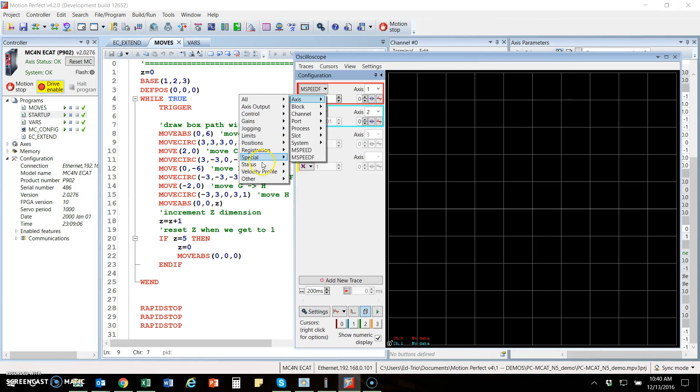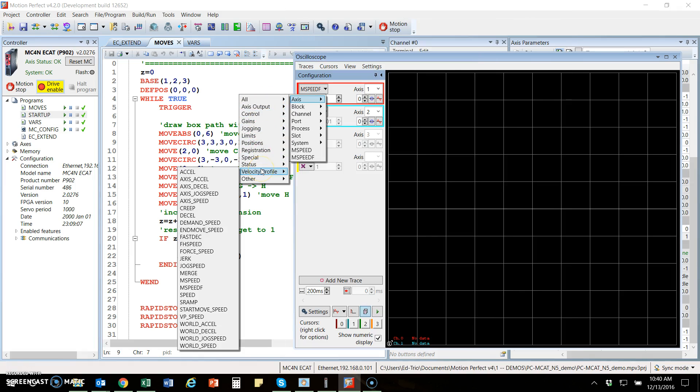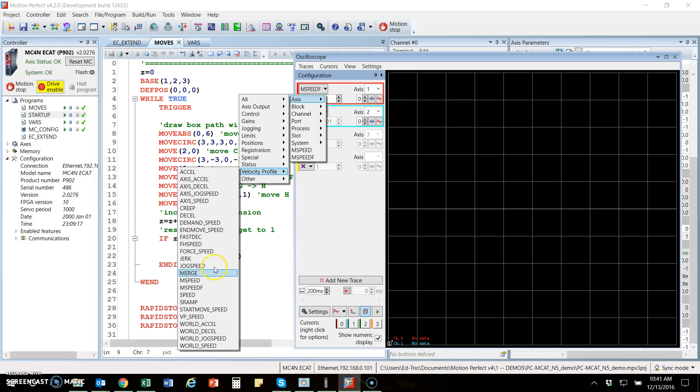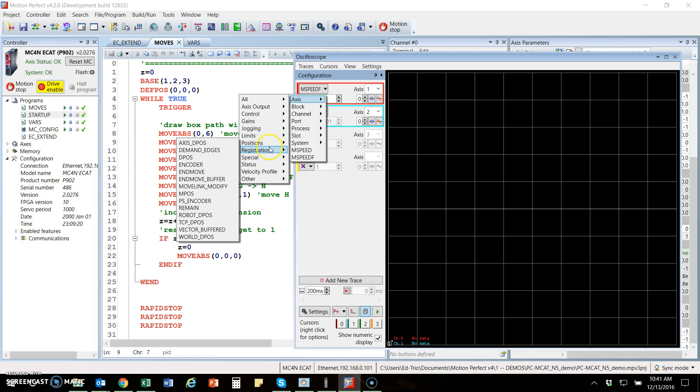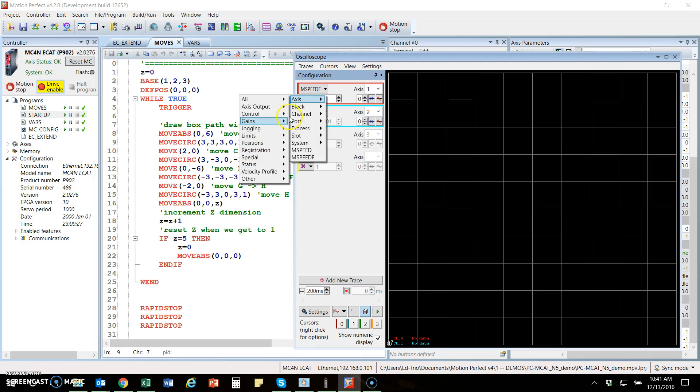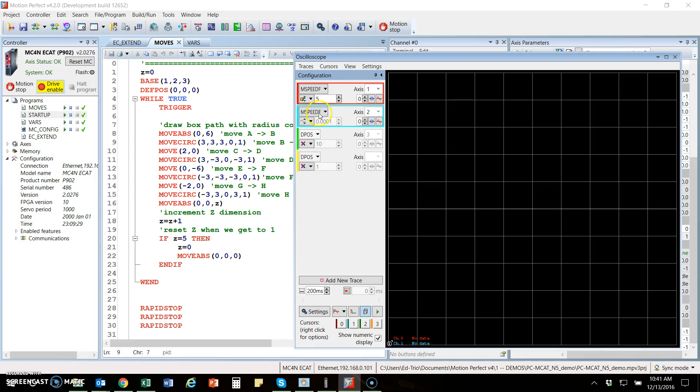Most of the time you're going to look at some velocity profiles, usually M speed or M speed F, which is a filtered M speed so it looks a little bit better. Also position-wise in that group, you'll look at typically MPOS, which is measure position or DPOS. In this case here, we're going to look at a couple of velocity profiles for axis one and two.